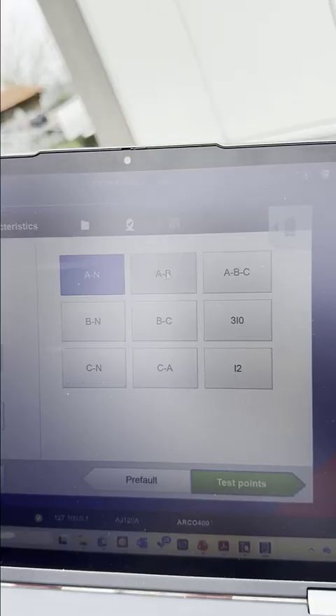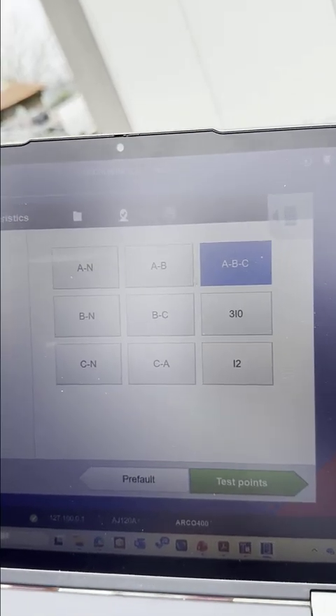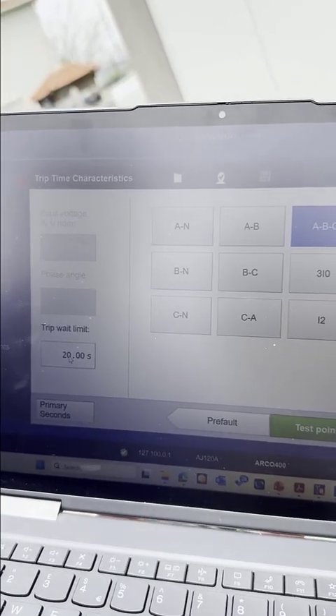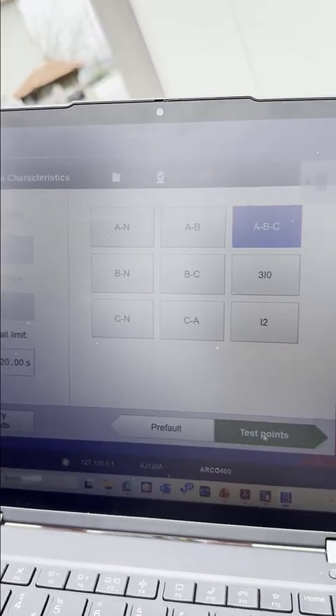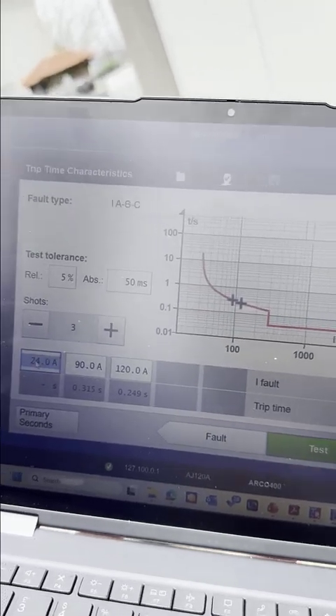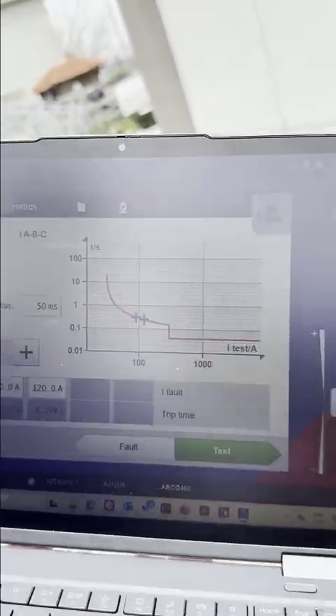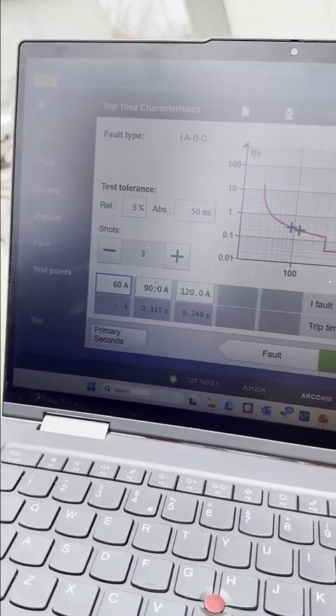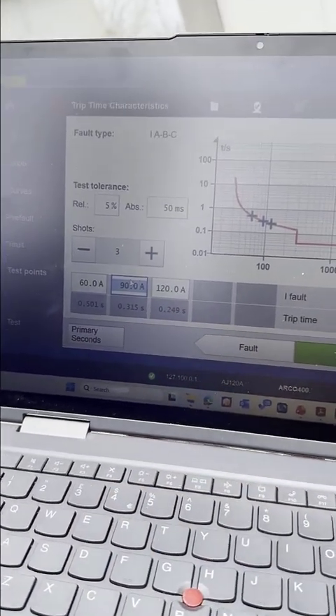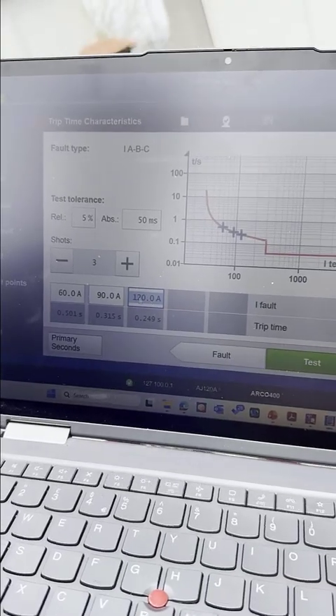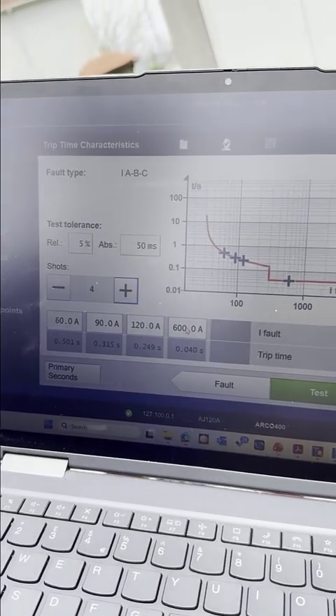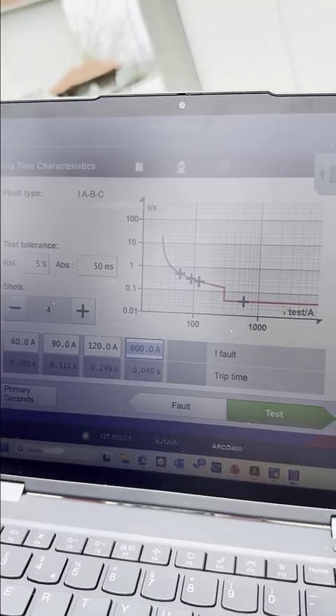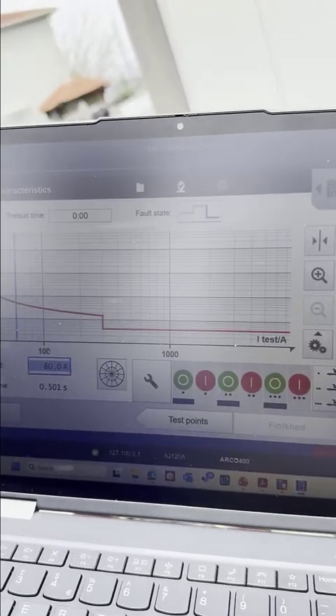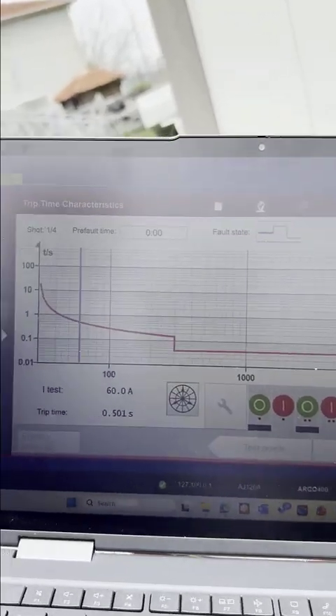Now you are free to select 3-phase fault or phase-to-phase fault loops, just to avoid interference with the earth fault protection. Also, the trip wait time should be longer than the maximum expected trip time, so 20 seconds is more than enough. Then we can select now the test shots. Since we are dealing with 30 amp, we can inject 60 amp for the first curve, and 90 amp, and 120 amp, and we can insert a new shot for the 600 to check this definite time stage. Then you can go for the test screen, you can click start.